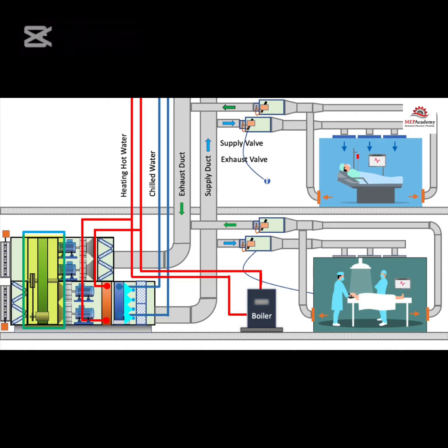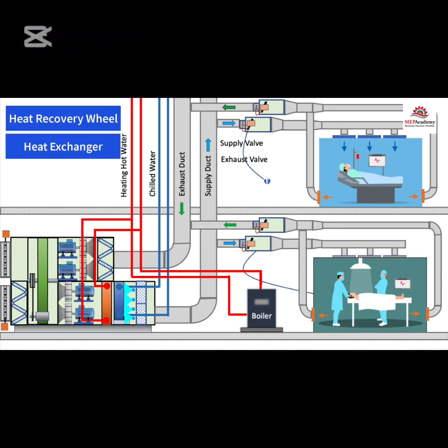Using 100% outside air is energy intensive, as we are spending energy to cool the air, and then we exhaust all of that air out of the building. To capture this energy, there are several choices like the heat recovery wheel, heat exchanger, or a runaround coil. We'll explain these in another video. We also added filters on the exhaust stream to keep the energy wheel clean.